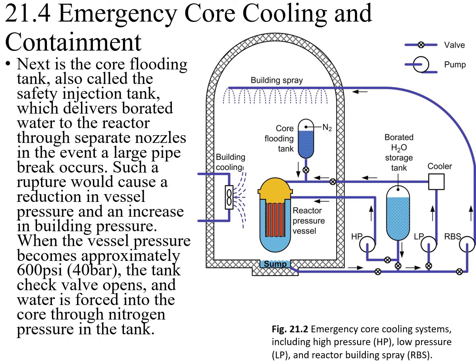The next one is the core flooding tank, which is shown here. This is also called the safety injection tank. This core flooding tank can deliver borated water to the reactor through separate nozzles in the event a large pipe break occurs. Such a rupture would cause a reduction in vessel pressure and an increase in building pressure. When the vessel pressure becomes approximately 600 psi or 40 bar, the tank check valve opens and water is forced into the core by nitrogen pressure in the tank. So this one uses compressed nitrogen, and it does not require electricity to operate. So after the high pressure injection system, if the pressure continues to drop, then later this core flooding tank will be activated.